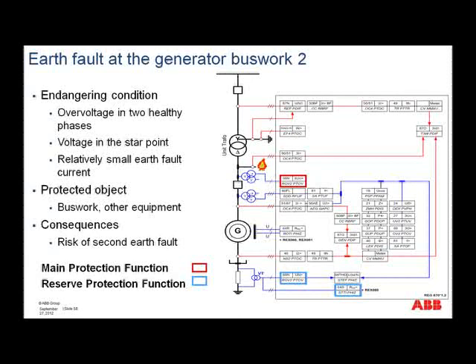This is just moving the earth fault a little bit down the buswork. And the main protection here, of course, would be the residual overvoltage protection. Once again, it would be possible to be seen by the overvoltage protection on the earthing resistor in the star point, and also the injection function could see it.